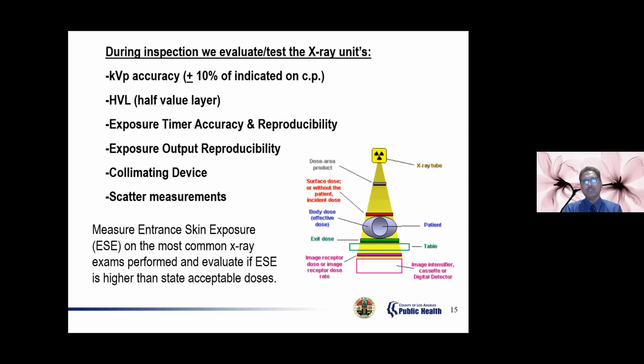That's what reproducibility is. It shouldn't vary from one exposure to the other. So we check that output reproducibility. Collimating device, it's that collimator that you go on the top there and you see the scale. If you put 10 by 12 or 12 by 14, whatever the size you're getting on the collimator there, what you see down here should be that size.